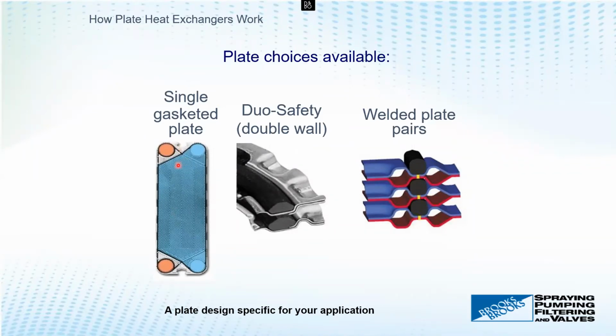Should you need additional protection to make absolutely sure that there is no way that the plates can contaminate, the headers are going to be fine, but what happens if there's a pinhole in the plate? What happens if something goes wrong with the plate? We can't have intermixing of the fluids. So there's a duo safety plate. Essentially, behind each plate, there is an added non-gasketed plate. And this air gap in between them means that should something escape from the plate in front of it, it will hit this non-gasketed plate behind it and then leak to atmosphere.